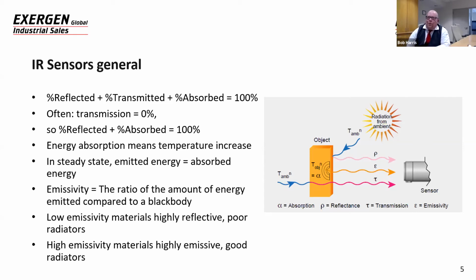So most objects that we measure are pretty solid. The only exceptions would be like a thin film or a semiconductor, where there may be some transmission of energy. But most of the objects that we're measuring are either reflecting or absorbing energy. So if you add up the percent of energy reflected plus the percent of energy absorbed, it'll equal 100%. And once that object absorbs all the energy, the temperature will increase. And the amount of energy that's absorbed is also equal to the amount of energy that's emitted when that object is at steady state.